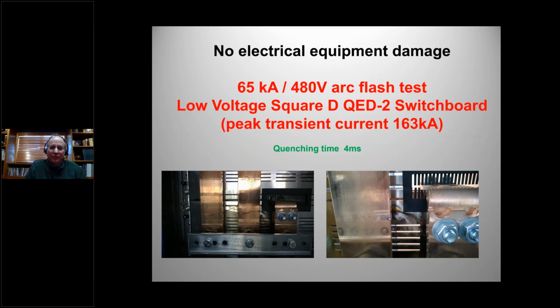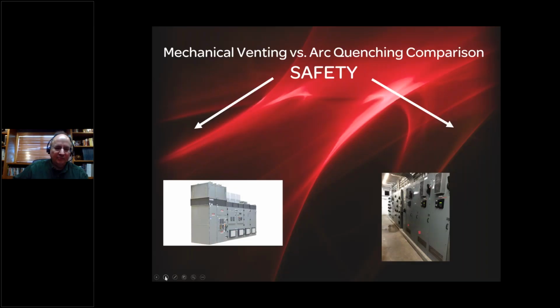That switchboard required approximately 20 minutes of maintenance to clean up the tracking on the bus, retest the equipment, and return it to service. And its service was to, because I can only afford one switchboard, perform the test on the right. Without the arc quencher, we've vaporized more than 32 pounds of copper in this event. So the switchboard on the right was damaged beyond the ability for practical field repair.